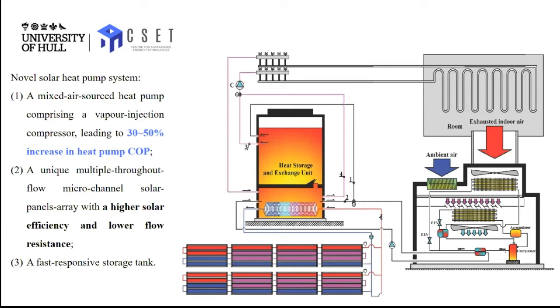In the morning, when the sun rises and heat demand is critically required by the house, we can quickly deliver the heated fluid into the room space for heating. That's why we call it fast responsive. And during the daytime, we got more and more solar radiation, and heat demand from the building is less and less. In this case, we alter the direction of the fluid, and have this low part fluid change flow direction and travel across the heat storage space, in which a significant amount of heat will be stored in the storage tank and the remaining heat delivered to the room space.